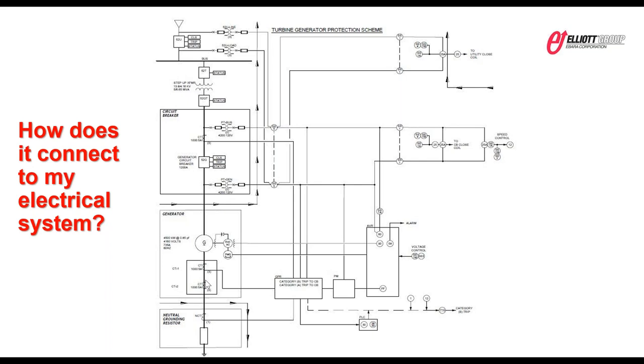Now, the leads or the electrical lines from the generator would connect into a circuit breaker or a switchgear type of device. With any sort of new generator into, say, a new system, we would be able to provide that circuit breaker, the panel that would be dedicated specifically for this turbine generator. Now, you may also have a case where the turbine is retrofitted into an existing facility and you have room in an existing breaker or switchgear where you can plug this unit in. But that control system, again, is going to take signals from all of that and make sure you're protecting this device properly.